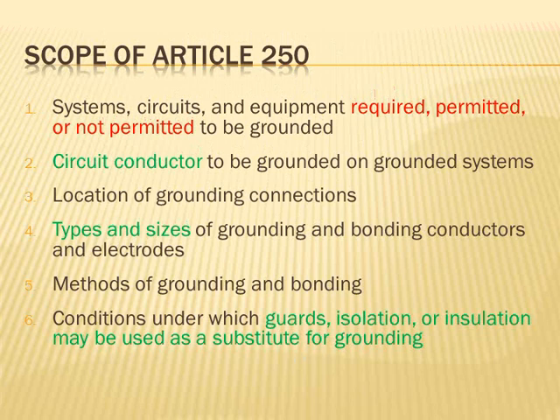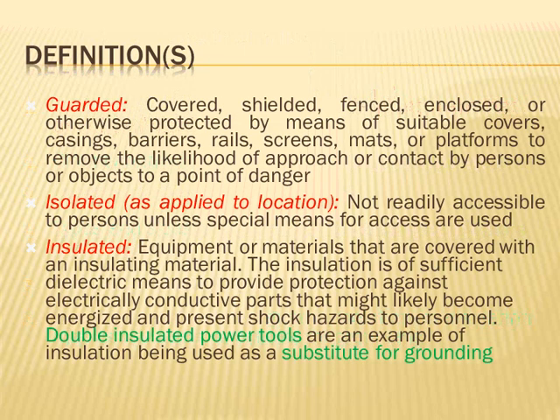That's when you isolate the system or insulate it, isolate it, or guard it with a fence. Isolate it typically with elevation. You put it in a mezzanine, 8 foot or higher. Then the code allows you, under certain circumstances, not to ground the frame of the equipment altogether. So these are very exceptional, guys. Here's the guarded, isolated, and insulated. I want to emphasize these are only, I would say, 2% of your situation. Maybe 5%. 95% of your situation is you have equipment that's grounded. Not systems, equipment. As in the panels are grounded, the frame of this equipment is grounded, and so forth.